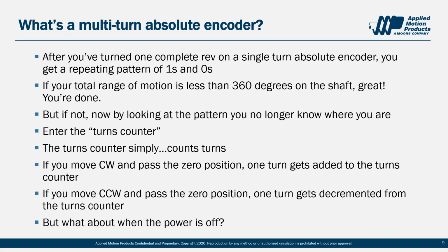This is the key advantage of the TruCount encoder. It can track drive position against the home position set at some point in the distant past, like machine commissioning. It can retain that information across power cycles, and it can even track motion which occurs when the drive is powered off.